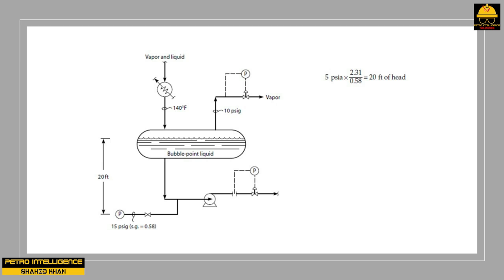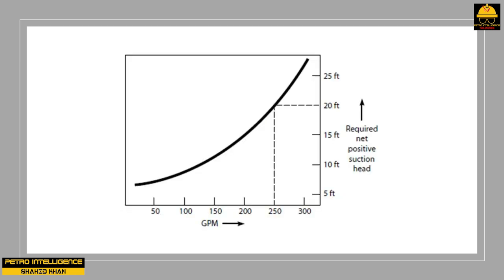The 20 feet matches the level of liquid in the drum above the suction line of the pump, and equals the available NPSH to the pump. The pump curve shows that at 250 GPM, the required NPSH of 20 feet equals the available NPSH of 20 feet. Therefore, at a flow rate of 250 GPM, the pump will cavitate.